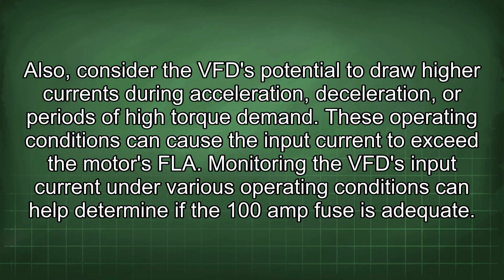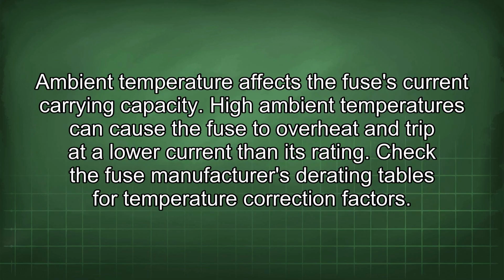Monitoring the VFD input current under various operating conditions can help determine if the 100 amp fuse is adequate. Ambient temperature affects the fuse's current carrying capacity. High ambient temperatures can cause the fuse to overheat and trip at a lower current than its rating. Check the fuse manufacturer's derating tables for temperature correction factors.